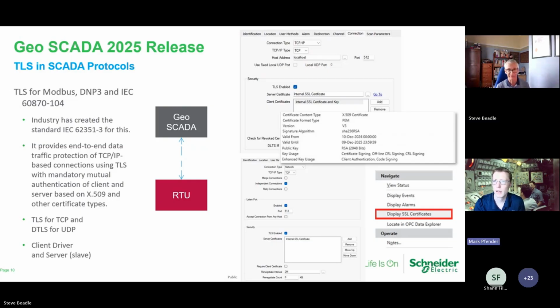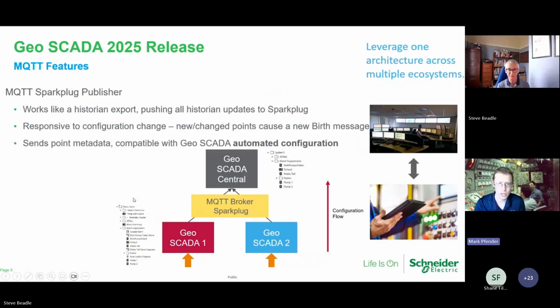Steve, could you go back one slide? Sure. I wanted to highlight an interesting use case for the gateway server, in that a lot of our clients have pump stations or lift stations, or essentially gateway stations where they have an RTU and a local HMI. And so one of the killer features of this could be running Geo SCADA on a local panel PC, building out your graphics mimics in that panel PC, and then syncing them with your central Geo SCADA database. And that way it aligns your field HMIs with your central Geo SCADA system to reduce the amount of configuration and increase the amount of control and configurability you have for each of the stations. Yeah.